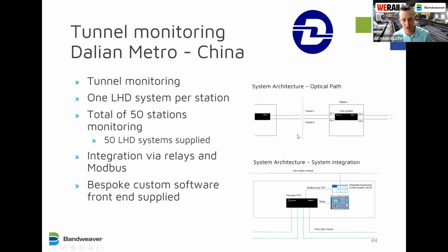In this case, the system was used for tunnel monitoring. There was 1 linear heat detection system per station. And if we look at this architecture on the right, you can see how it's set up. It was a 4-channel system with 2 channels going either side, monitoring one of the 2 tunnels. It monitored to the halfway point between the next station, at which point the neighboring station would take over the other section of the tunnel. And this was the architecture that the customer wanted, that every station was completely independent, self-sufficient, integrated. So there was 50 stations installed, so 50 LHD systems.